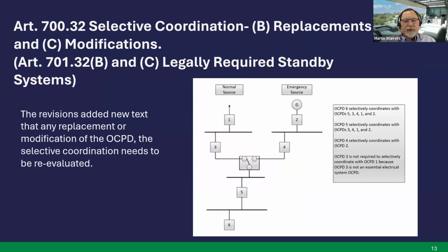Article 700.32, selective coordination, both B, replacement, and C, modification. Same language in 701.32, B and C for legally required standby systems. The revisions added new text that for any replacement or modification of the overcurrent protection device, the selective coordination needs to be reevaluated. Next slide.